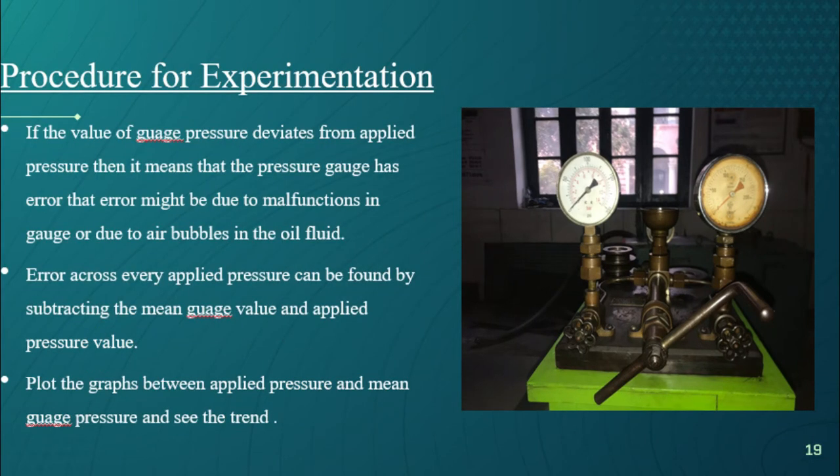If the value of gauge pressure deviates from applied pressure, then it means that the pressure gauge has error. That error might be due to malfunctions in gauge or due to air bubbles in the oil fluid. Error across every applied pressure can be found by subtracting the mean gauge value and applied pressure value.